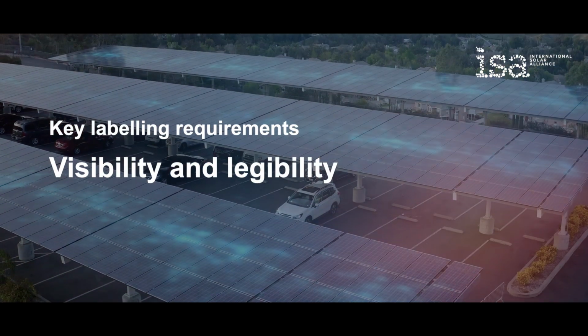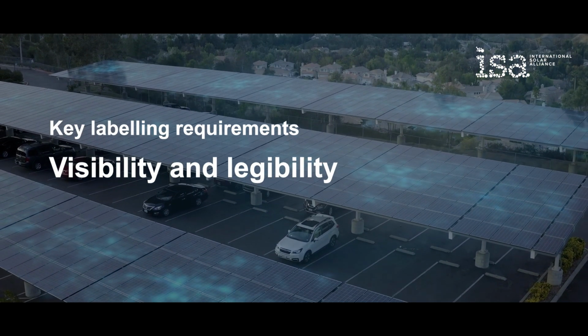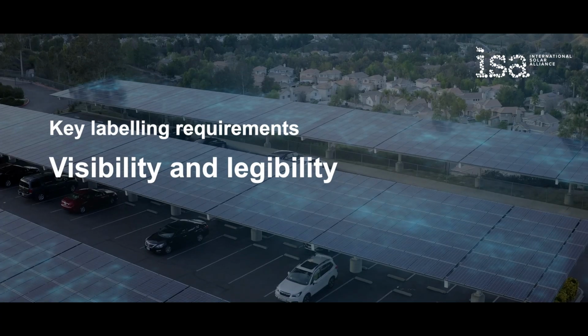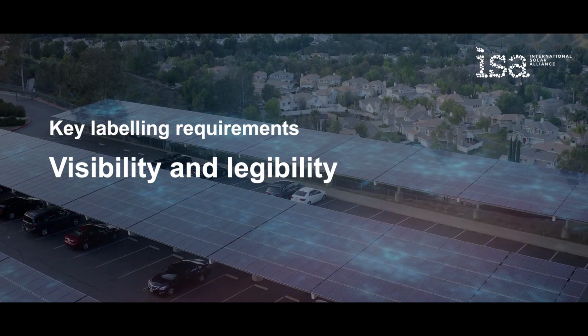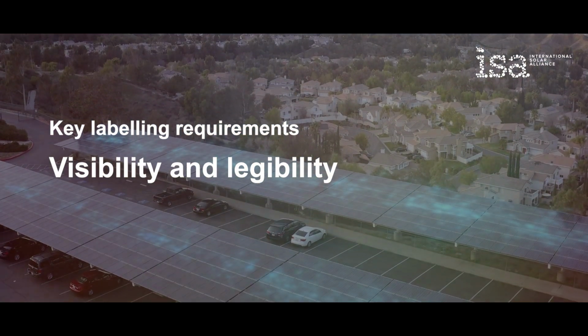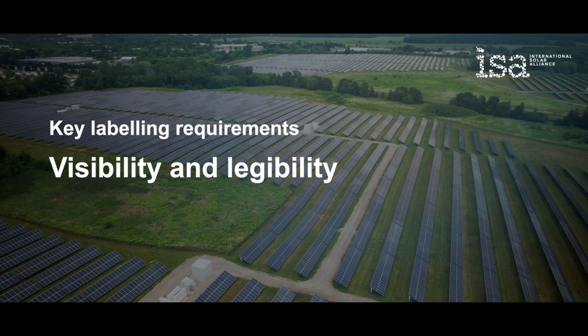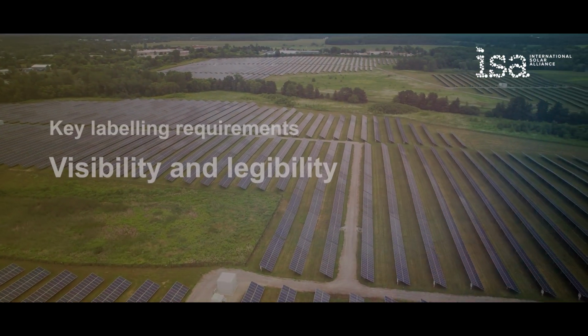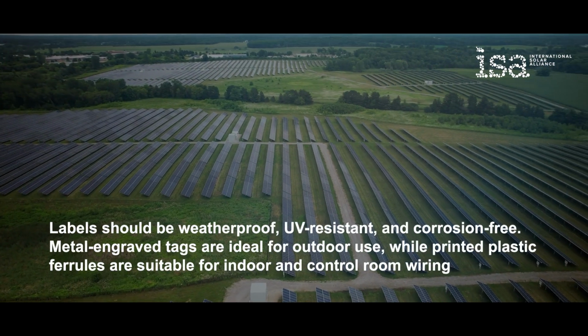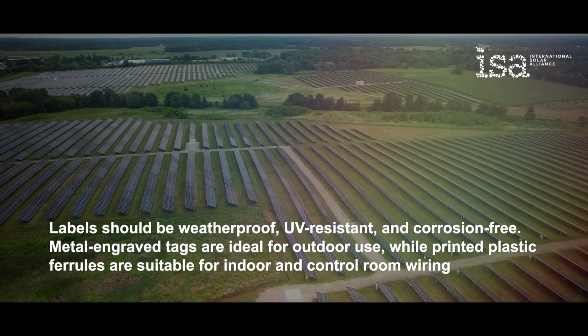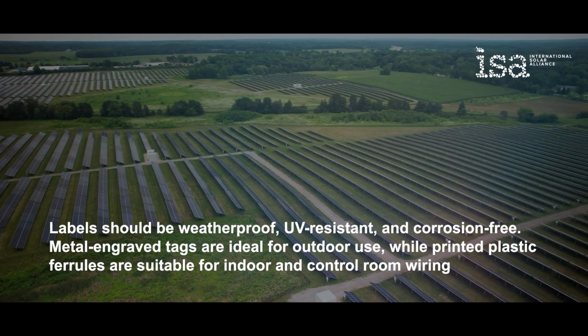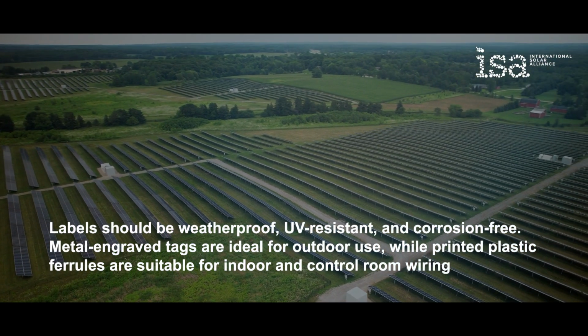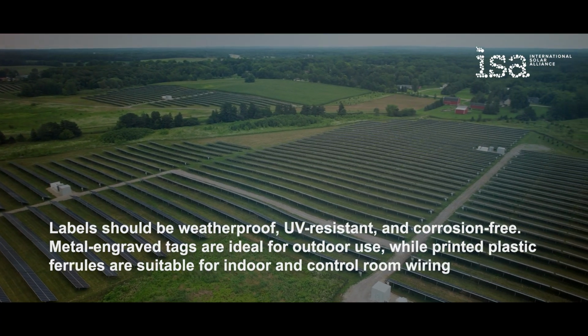Labels should be permanently affixed, legible, and visible after installation. Many codes require reflective properties and a minimum text size, such as 3/8 inch, 9.5 millimeters tall, using white text on a red background. Labels should be weatherproof, UV resistant, and corrosion-free. Metal engraved tags are ideal for outdoor use, while printed plastic ferrules are suitable for indoor and control room wiring.